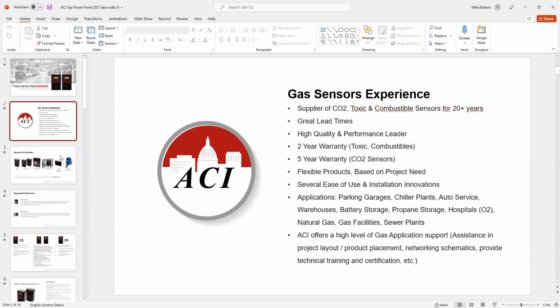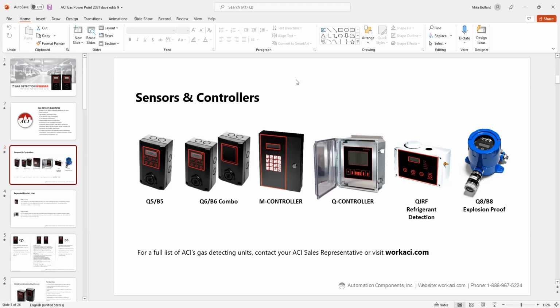So next screen is just a basic sensor and controller overview. We'll get into more details as we get down in the webinar here, and feel free to stop me at any time if you guys have questions. The Q5 is basically an analog and an RS-485, RS communicating. The B5 is our BACnet version of the same toxic and combustibles. Q6 and B6 is the same as the Q5 except for their combo units. M controller is our smaller controller that can handle up to 32 sensors. And the Q controller is our larger one that can handle up to 128 sensors on one job, and can also be set up to have BACnet IP if needed.